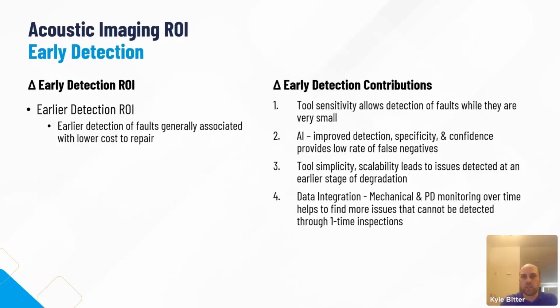This also speaks to tool sensitivity and improved detection via AI, so you have confidence that the data you're collecting is accurate. You eliminate false positives. Know that the CFM you're collecting is accurate, know the decibel reading you're getting from a mechanical asset is accurate. From there we can help you quantify, help with condition-based monitoring, and start trending that data.